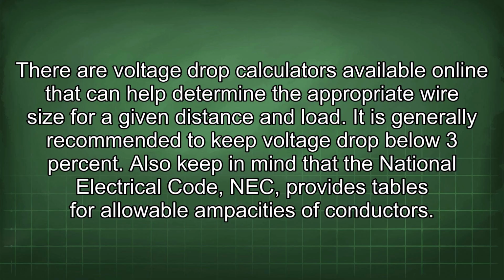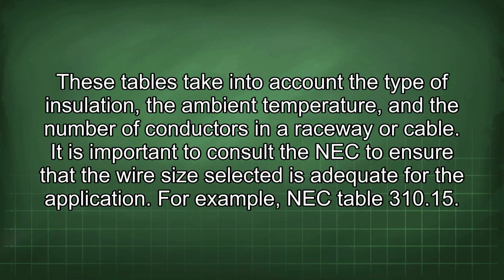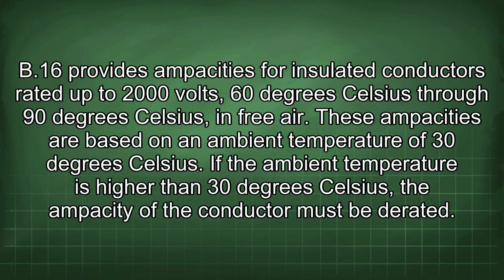Also keep in mind that the National Electrical Code, NEC, provides tables for allowable ampacities of conductors. These tables take into account the type of insulation, the ambient temperature, and the number of conductors in a raceway or cable. It is important to consult the NEC to ensure that the wire size selected is adequate for the application. For example, NEC Table 310.15(B)(16) provides ampacities for insulated conductors rated up to 2000 volts, 60 degrees Celsius through 90 degrees Celsius in free air. These ampacities are based on an ambient temperature of 30 degrees Celsius. If the ambient temperature is higher than 30 degrees Celsius, the ampacity of the conductor must be derated.